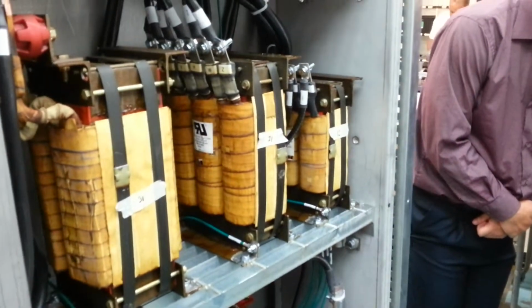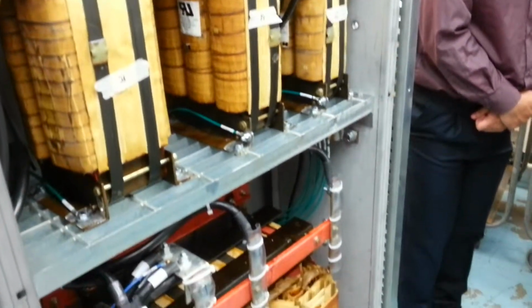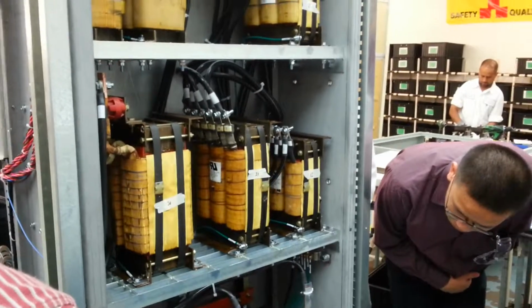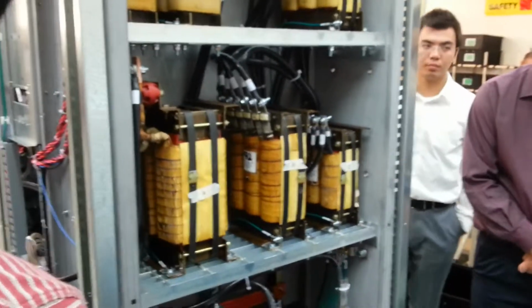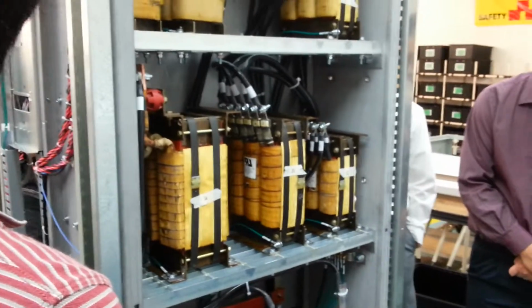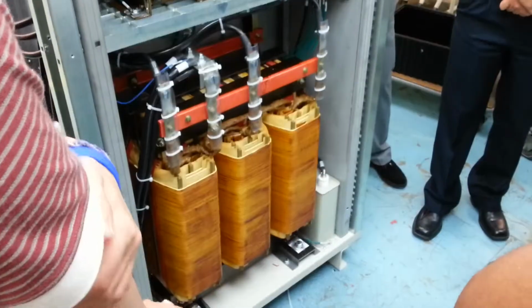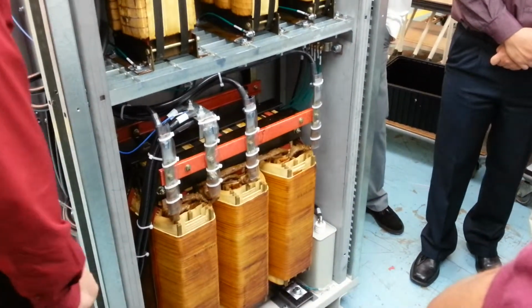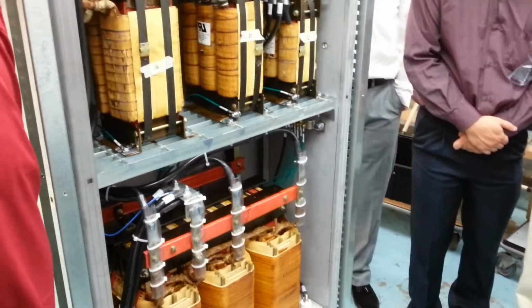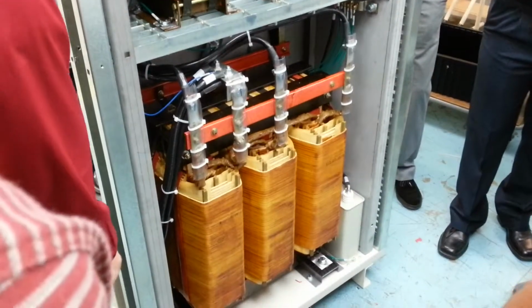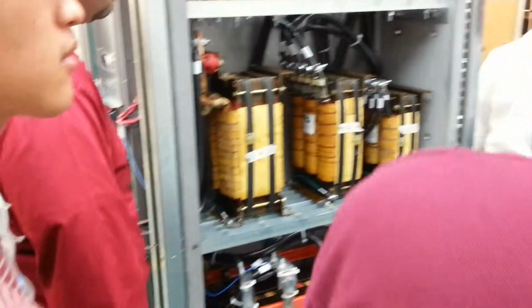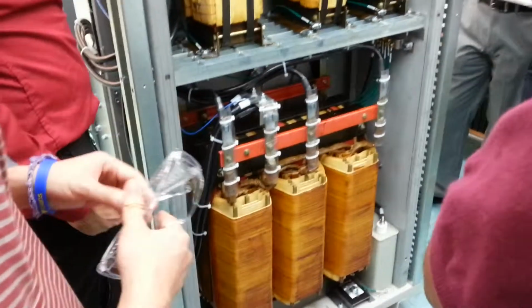They actually have to make, fine-tune, and associate the actual LC filters. So here's our L and our C. So each reactor is associated for either the first, third, fifth harmonic region associated with the L filter. And on the output, we have a transformer that's also a step down, in this case step up transformer from 300 to 480. And on the output, the transformer also has a 6.5% impedance. So the transformer on the output is now our output L, and we have a C on the outside. Okay. So that is our L. So on the input, there's your L, C, output, L, C. So the transformer also has that inductance built into it.